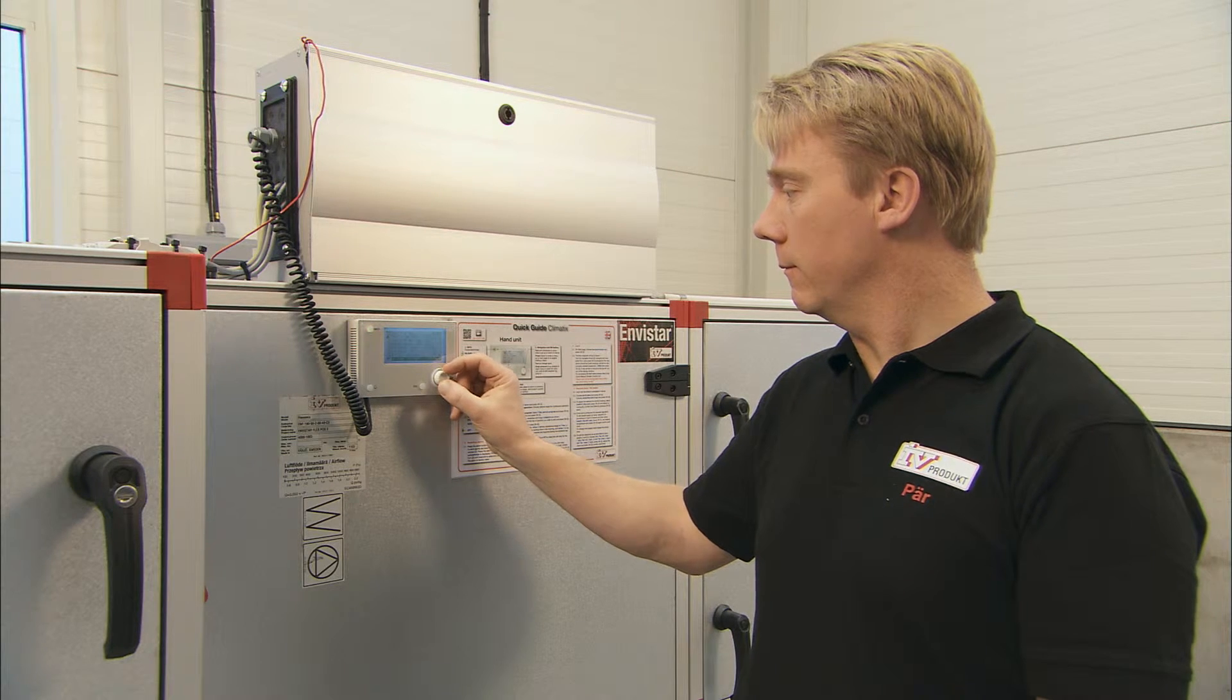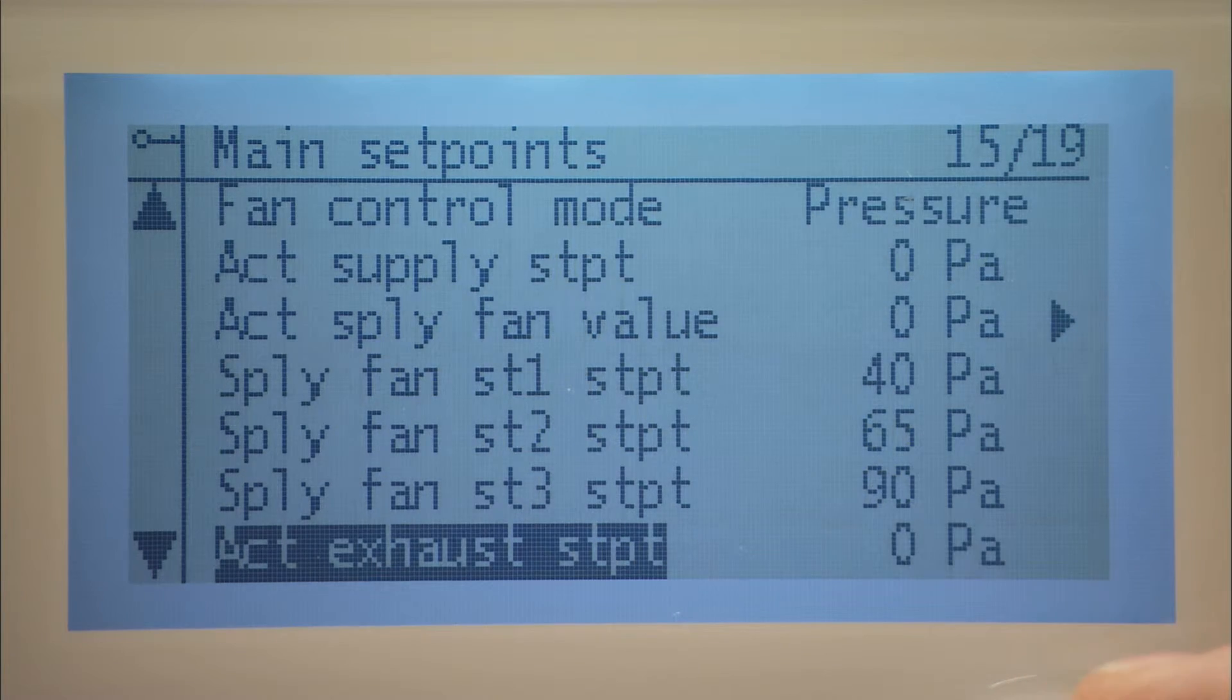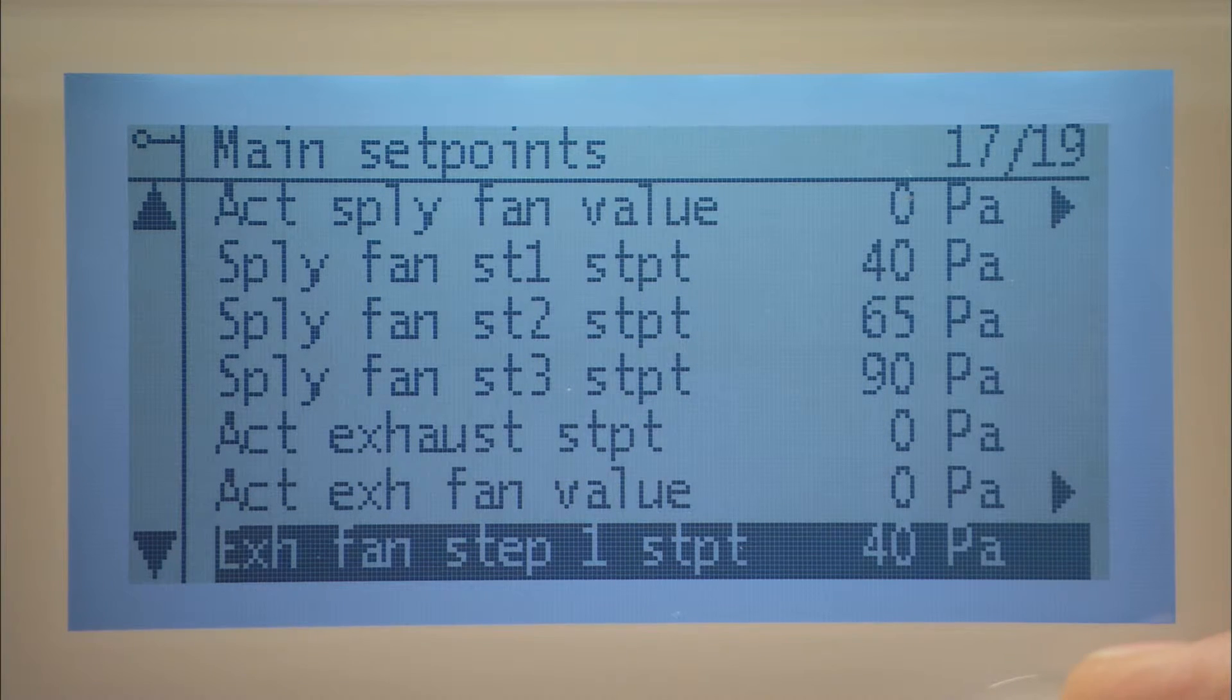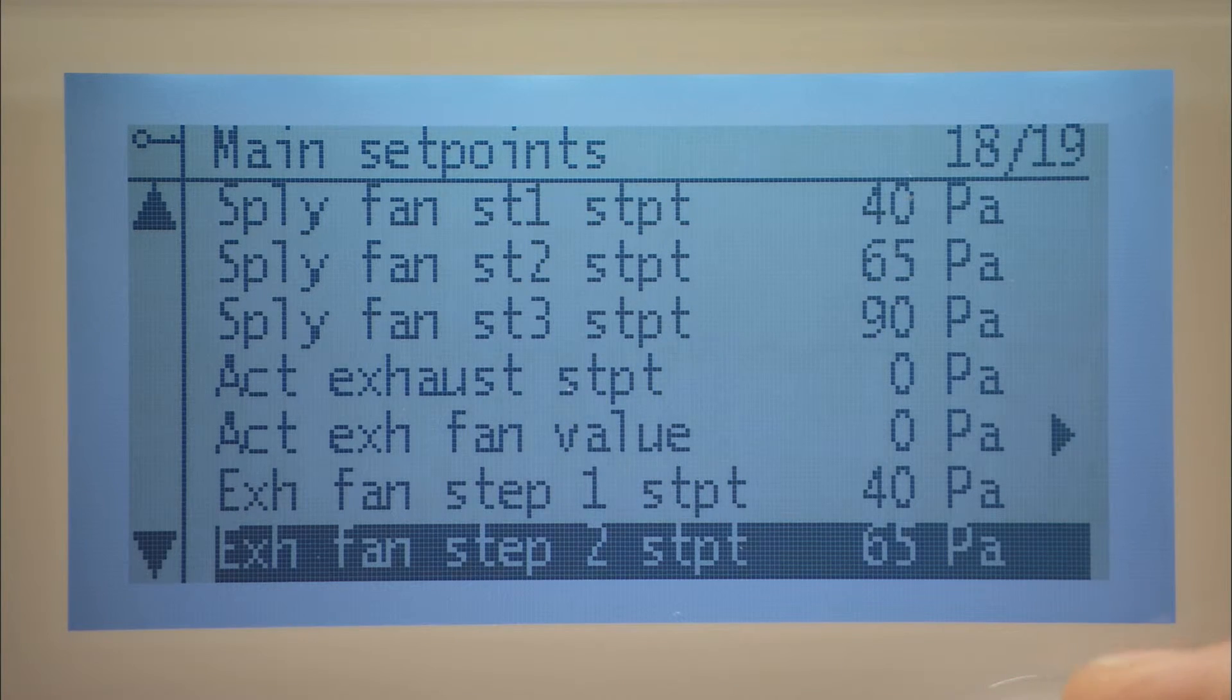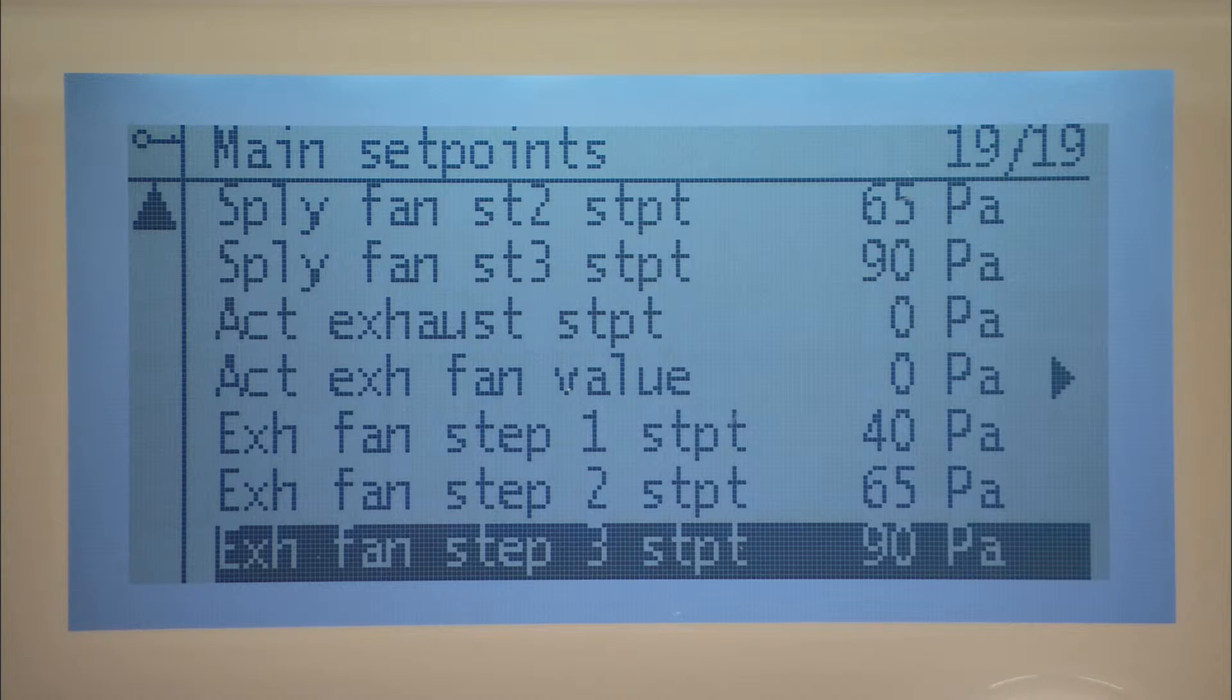It is possible to set three different air flows or air pressures for the ventilation if the unit is configured for three stages when supplied. These are called stage one, stage two and stage three. By assigning these different values, you can achieve different volumes of air at different time intervals.